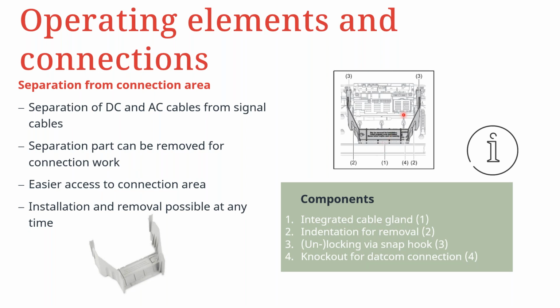The separator itself can actually be removed when you're doing your installation to make the work easier. And the fitting of the same is actually quite easy. So we can see here the various components that are related to the separator: the integrated cable gland, the indentation for removal, then the unlocking via the snap hook, whereby the separator is secured in the inverter. And then we have position 4, which allows for a knockout for data communication cables.